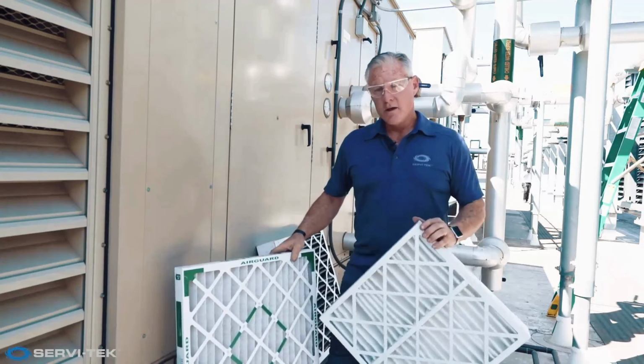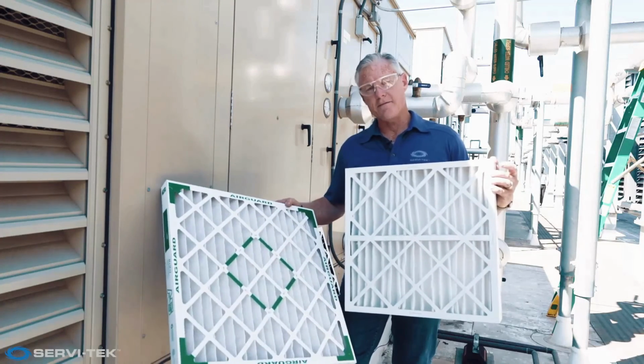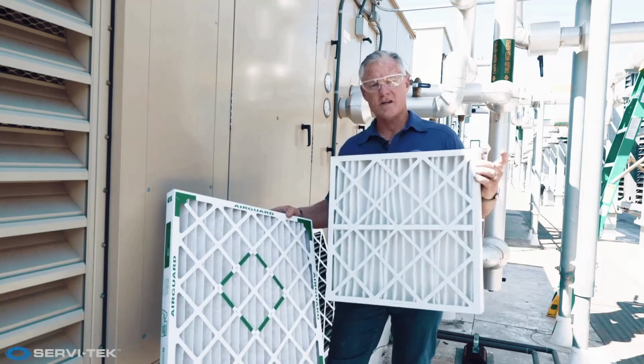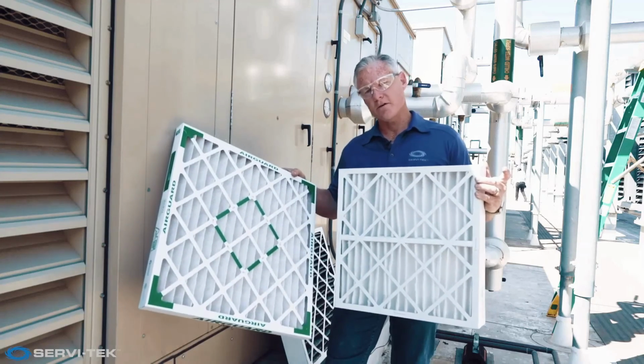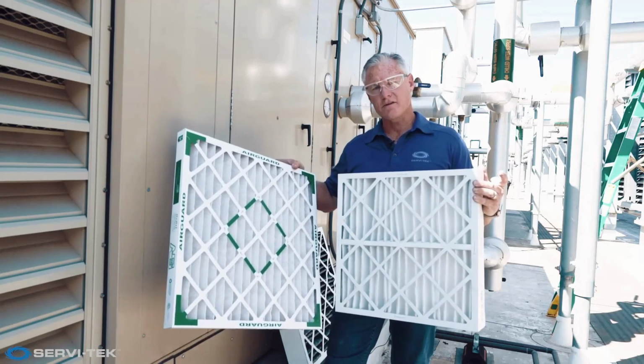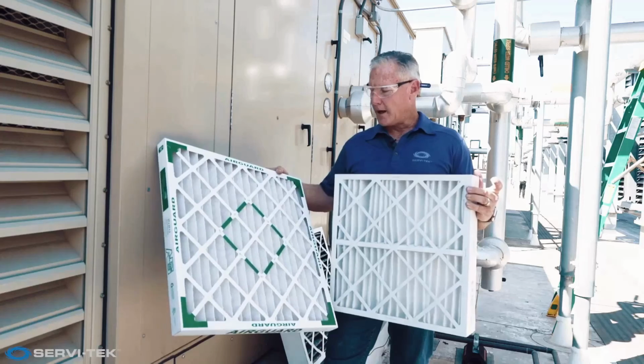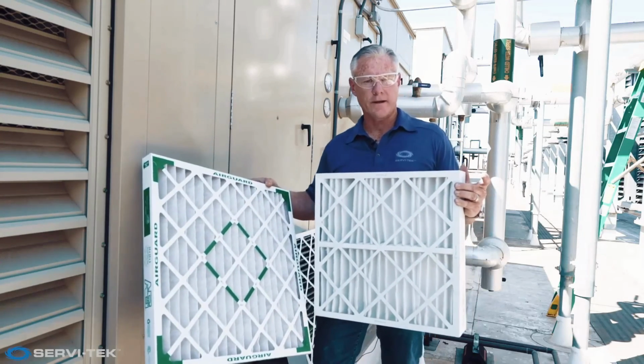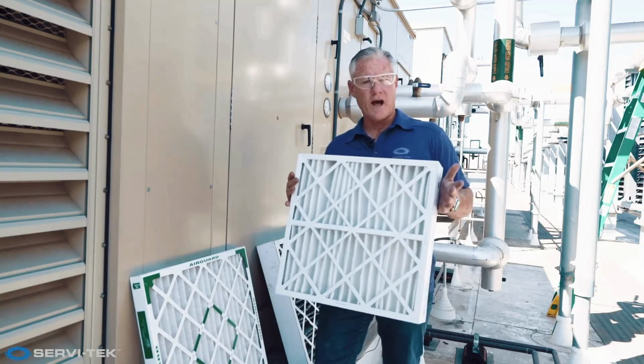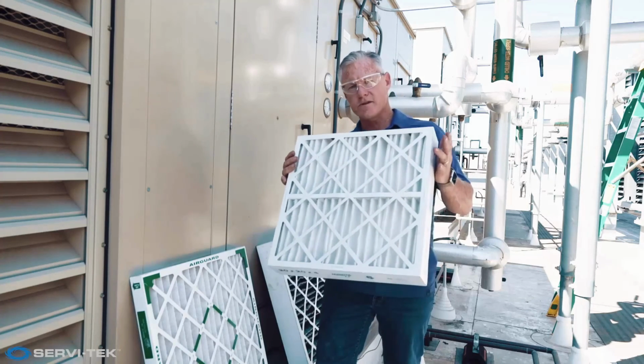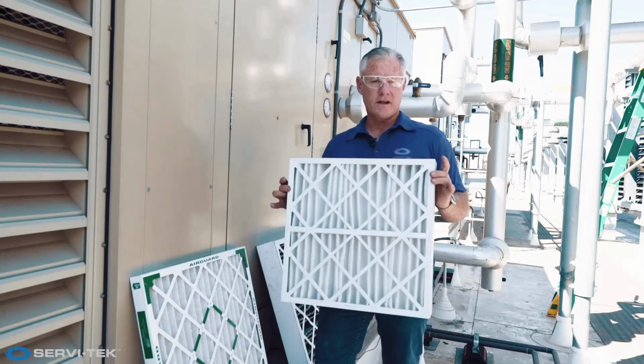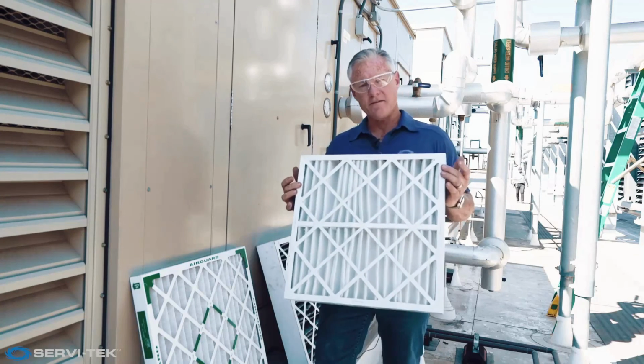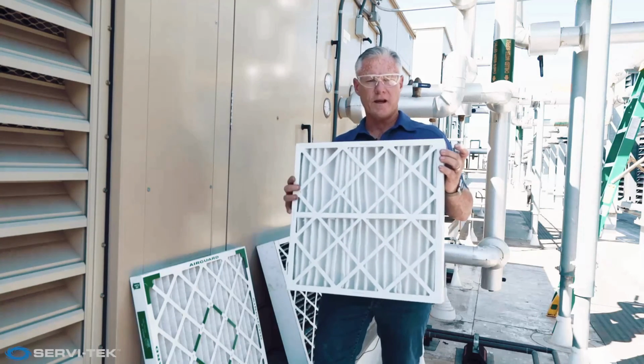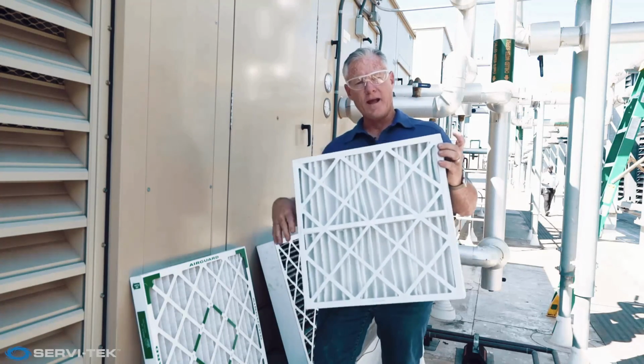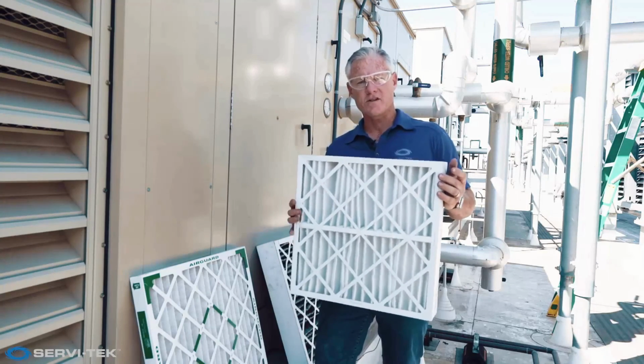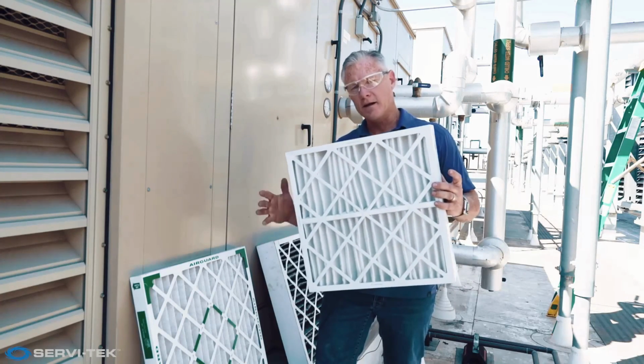So the difference between a MERV 13 filter and a MERV 8 filter is that a MERV 13 filter is actually rated to filter viruses, where the MERV 8 filter will not. This is a residential standard filter, as well as a lot of light commercial up to standard pre-filter in larger commercial buildings. This filter will filter a lot more bacteria, viruses, germs, dust, pollen. So MERV 13s are really good filters, but understand that a MERV 13 is a charged filter. That means the filter medium itself is a charged medium, and it will deplete over about 2 to 3 months, and the rating will drop to about a MERV 10, MERV 11 rating.